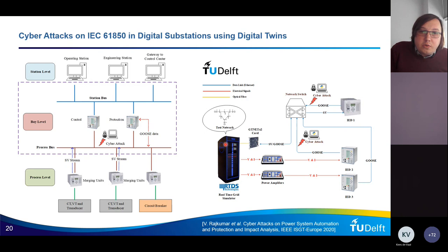We could simulate a short circuit in the RTDS. The sample values would be communicated to, let's say, in this case, IED1. IED1 would detect the short circuit by running its algorithm, and then would send a GOOSE packet to open the circuit breaker that is simulated in RTDS. Of course, in this environment, we don't have a power grid infrastructure. So everything is simulated in the real-time digital simulator.